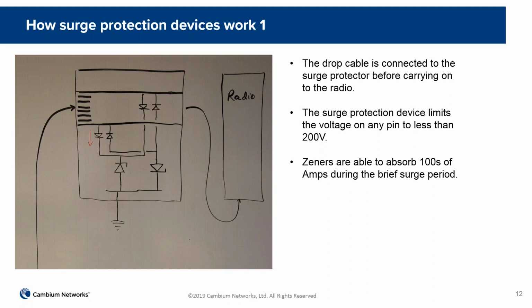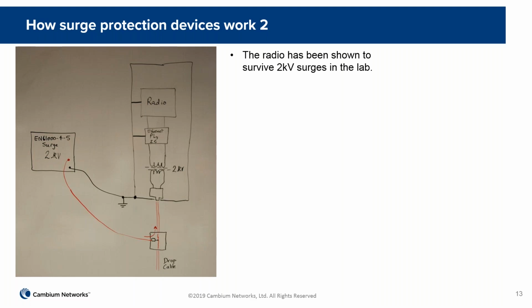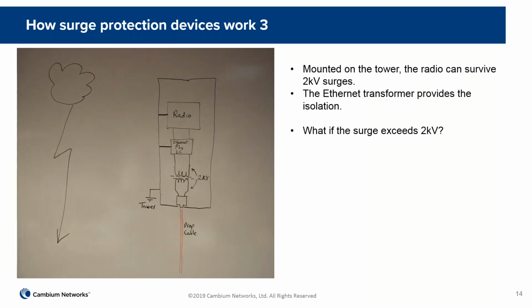So what these surge protection devices do is to limit the voltage on any of those pins. They clamp it to ground, in effect, and make sure it doesn't exceed typically about 200 volts. So that's an order of magnitude less than the breakdown voltage that we've already determined the radio is capable of withstanding. So as I mentioned, the radio can survive the 2 kV surge, and so when we have that radio on the tower, providing our surge doesn't exceed 2 kV, everything should be okay.